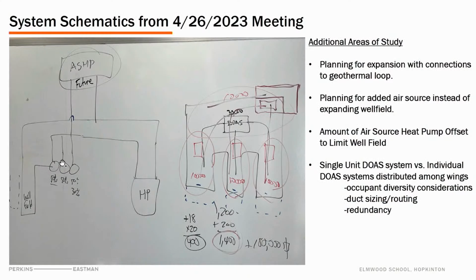This is what I was drawing here: my ground source loop. My well field was out here, and I've got pumps that pump the water in and out into the individual heat pumps, which represents all the heat pumps in the building. So if this thing starts to run out of capacity, I can tack on an air source heat pump, which is effectively a chiller that can take heat away or add heat to that loop.